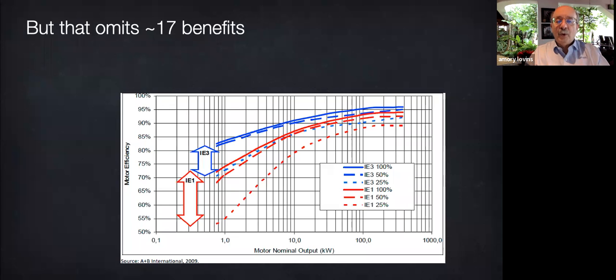The right-sized new motors will also cost less upfront because although price does not correlate with efficiency, it certainly correlates with size. Rarely upsizing is worthwhile, often to speed processes, but usually right size means one or maybe two frame sizes smaller than the motor that's there now, occasionally three. And the flatter efficiency curve across the load range, hence over the integrated varying loads, also improves flexibility as well as saving energy. Premium motors have higher and flatter power factor too. That's a measure of how much voltage and phase are out of step with current, causing reactive power loads that you have to pay to generate and transmit, but you can't charge for them. So it hurts the utility and it heats your equipment.